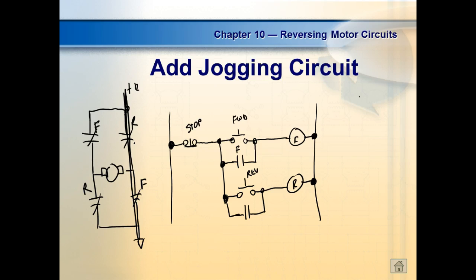And somebody would do that, right? So what do y'all think we need to do to prevent this from happening? Like an override. What do you mean by an override? So it won't allow you to press both buttons at the same time? We've got that capability. We've got what we call mechanical interlocks that we could put. Well, what we would do is I would come up here, right here, and I'd put a contact right here, normally closed, and I would give this to R, and then I'd come down here and put a normally closed right there, and this belongs to F.